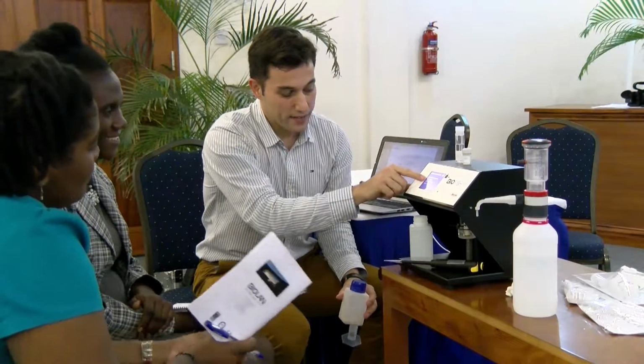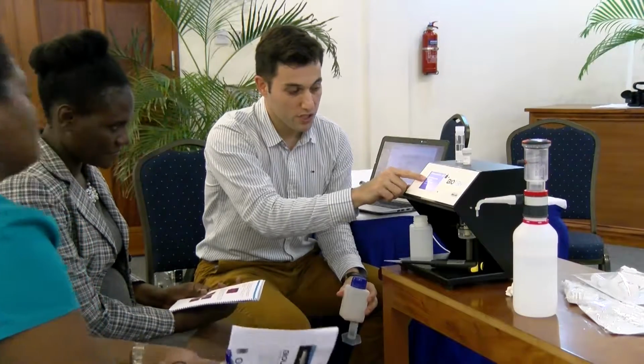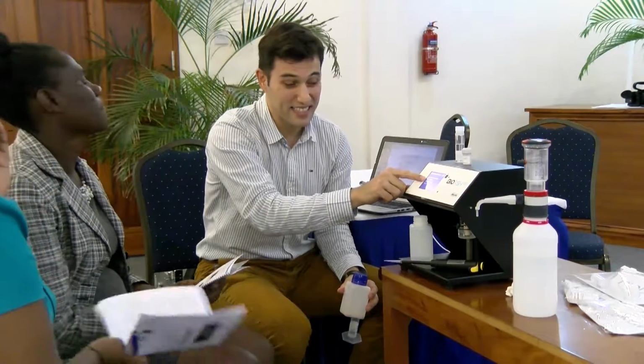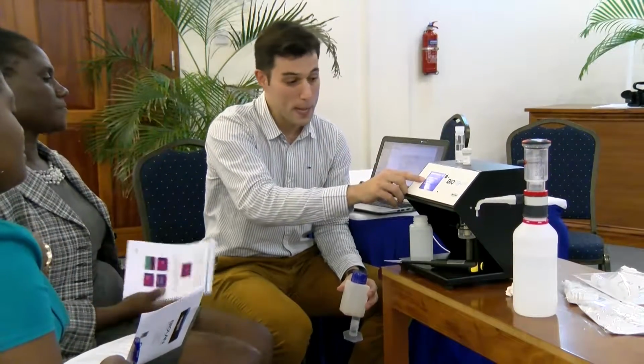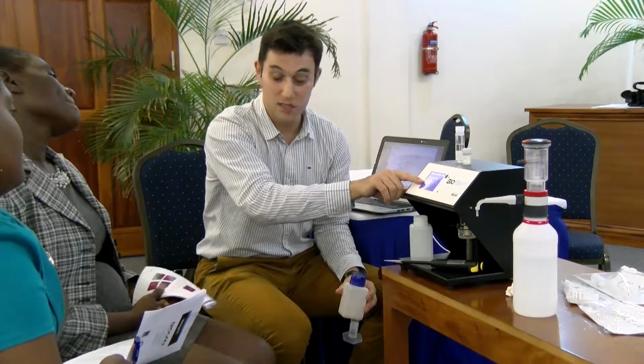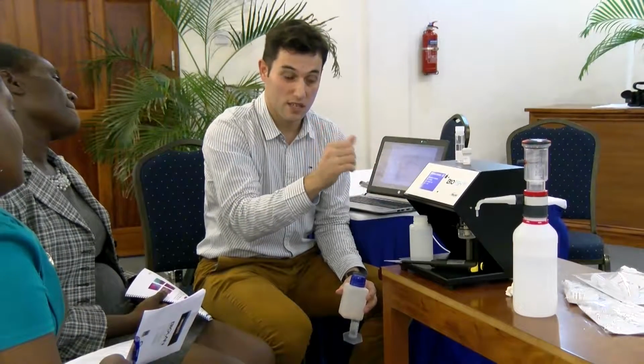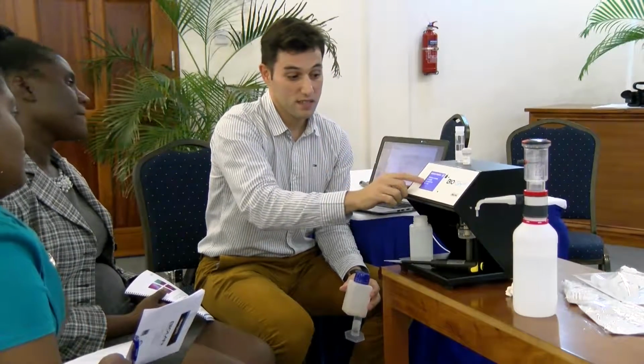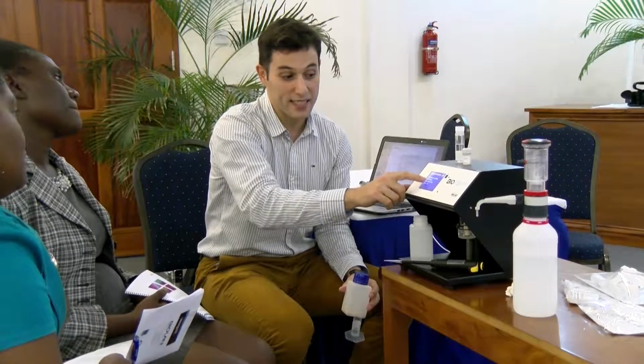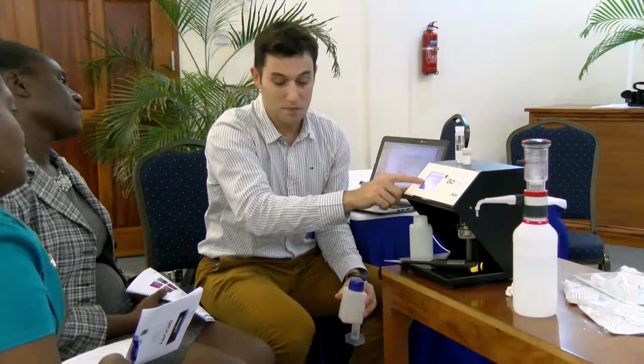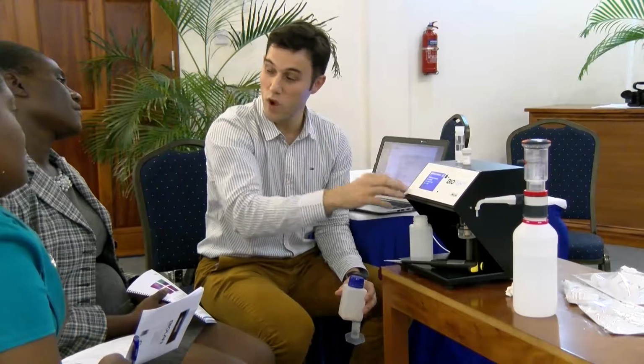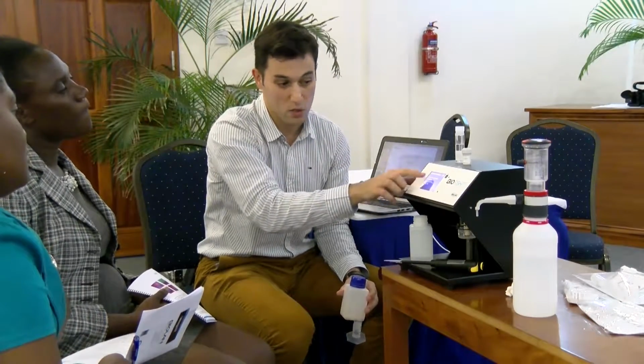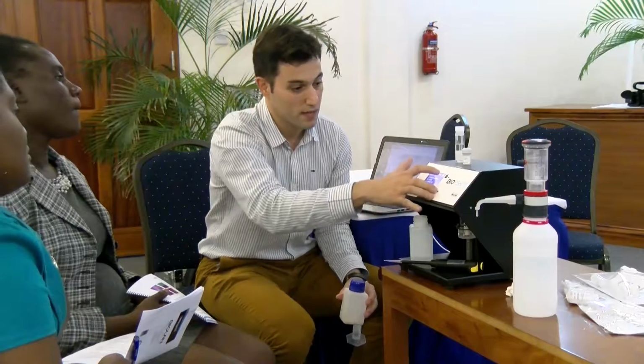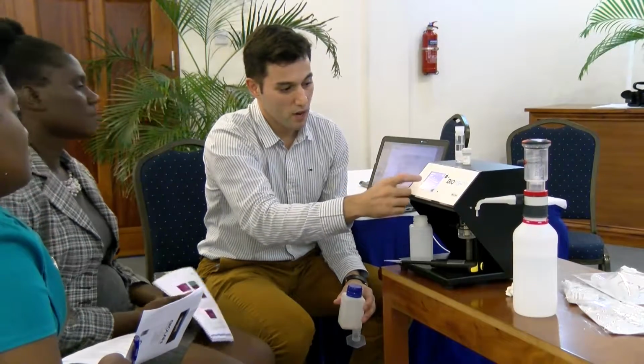You have here R. The R tells us how good the calibration line is. It's a linear regression. And M is the second parameter, which is very important because it tells us the slope of the line. R must be at least 0.999, and M must be above 150,000. If the two conditions are met, no problem. Then now we can go ahead with the sample.